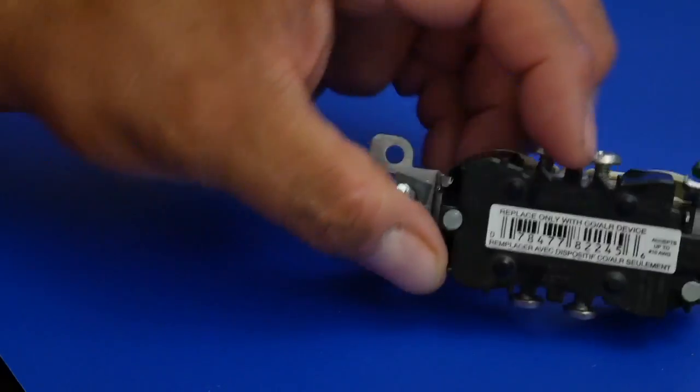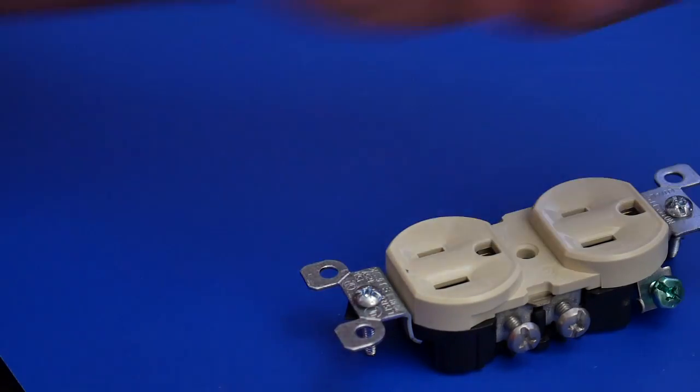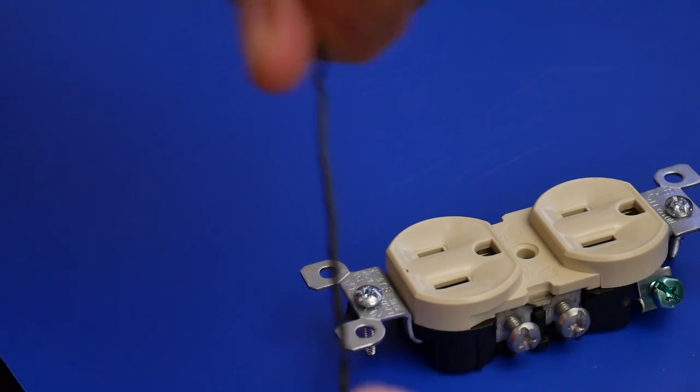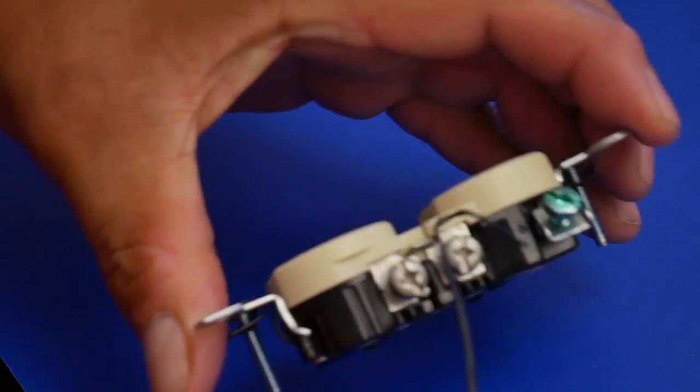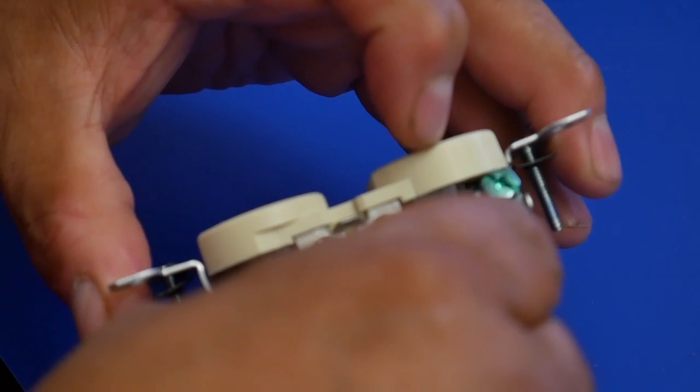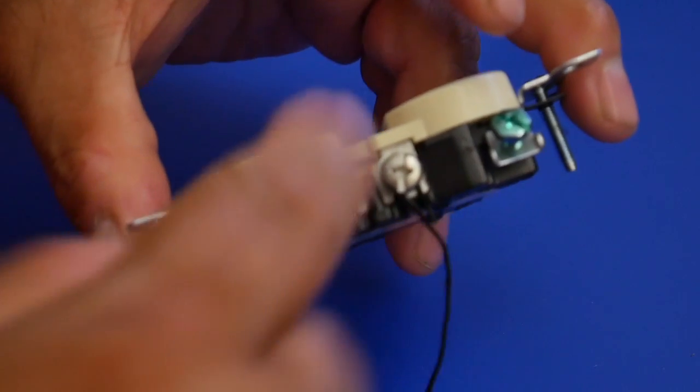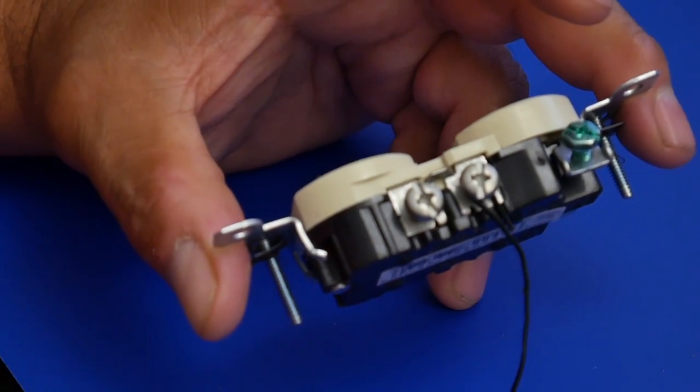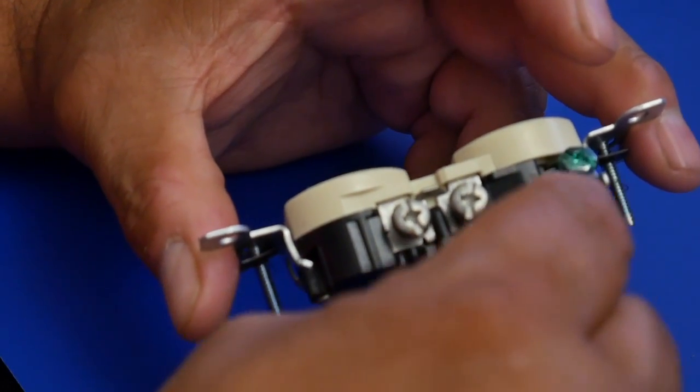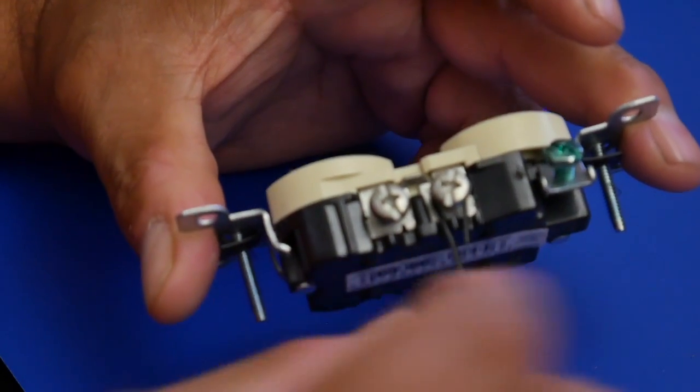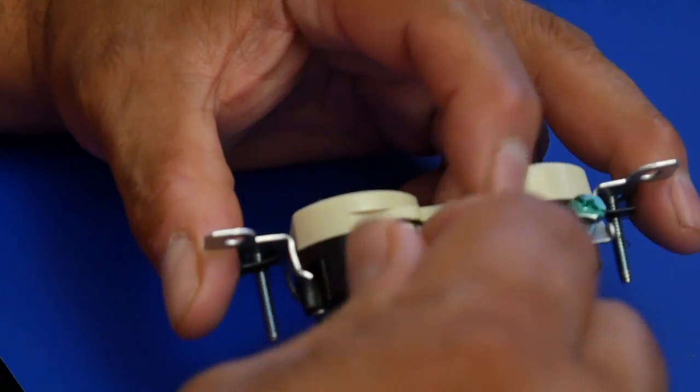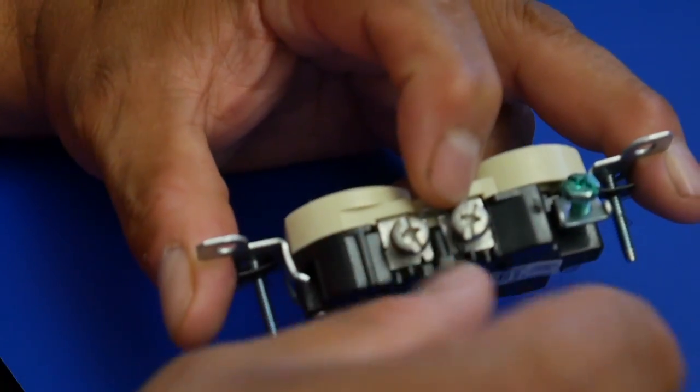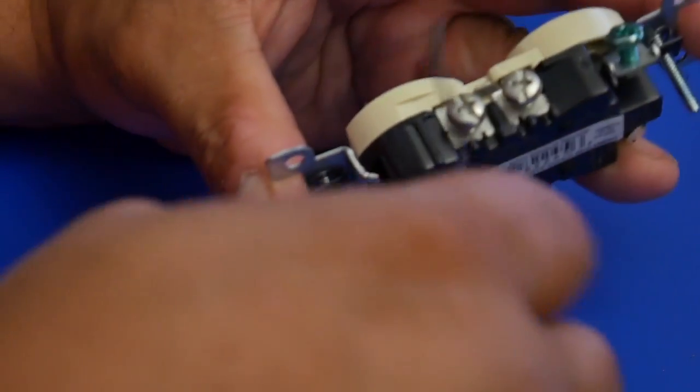One of the last things I'd like to point out: when you do put the wiring around—this is just for illustration purposes—when you do put the wiring around one of these set screws, you're going to actually wrap it in the direction the set screw turns. The other thing that you're going to do is you're going to take a little pair of pliers or something and you're going to try to squish the wire where it wraps real tight, and then you're going to set the set screw down. That would be for proper installation. You're not trying to just leave it open like this if you can help it. You're trying to wrap it around tight like this. The bare wire—and there is a little position here to be set in where the wire sets in nice and tight. I have seen where some people have actually just put a wire and set it in like this. I'm not going to say that's a proper installation. You want to wrap it around, screw in the direction it closes. That would be proper installation.